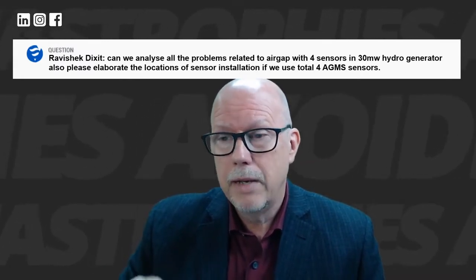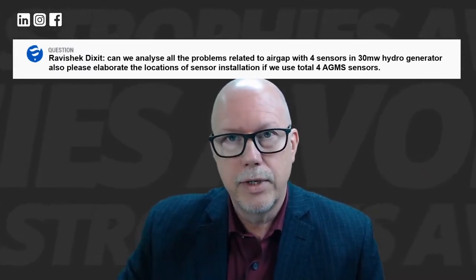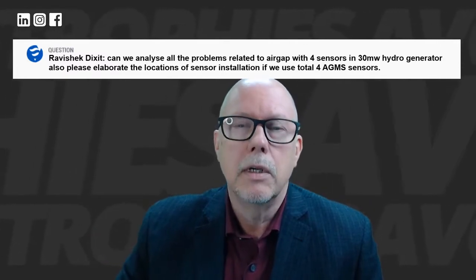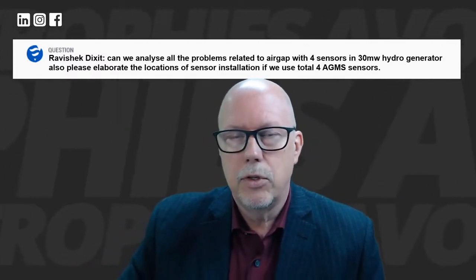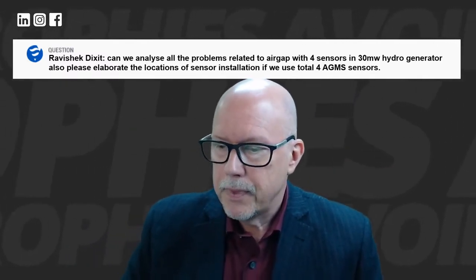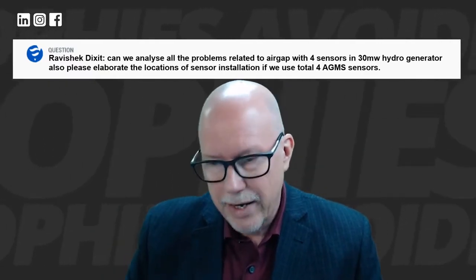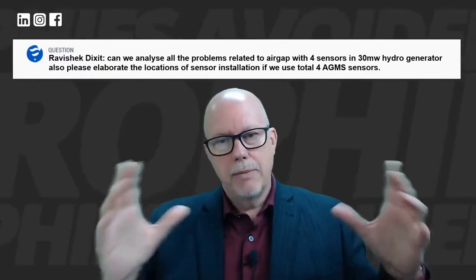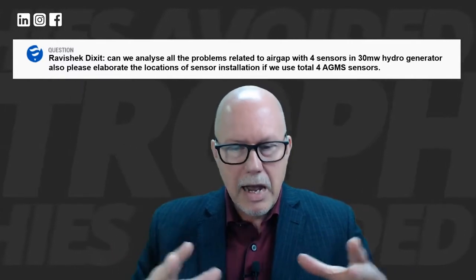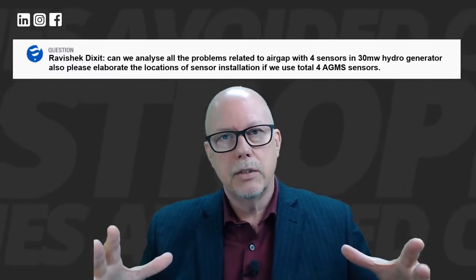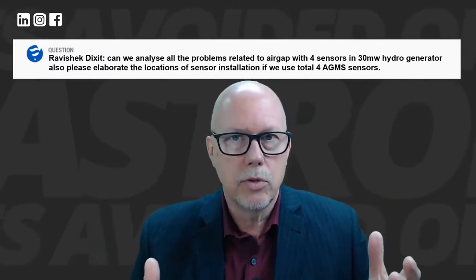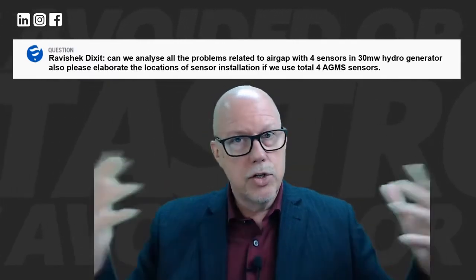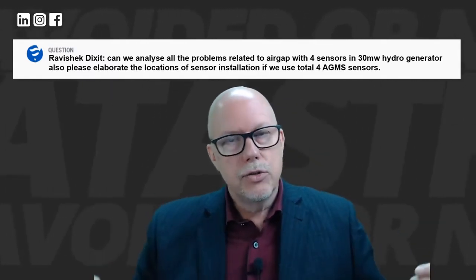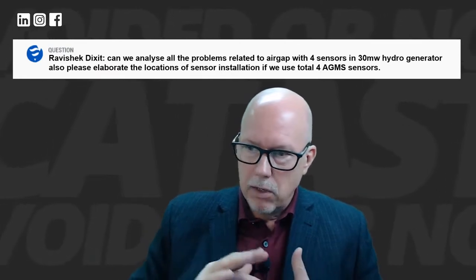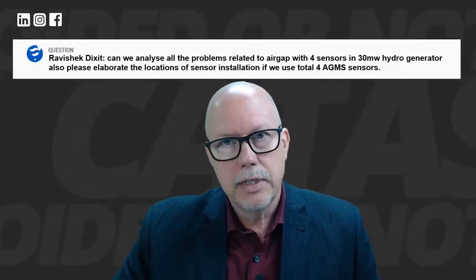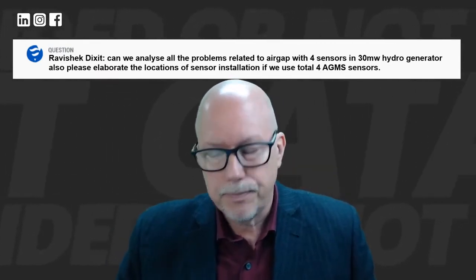I mean, the OEM has to validate that what they're delivering actually works as promised. You can't do that if you don't have any data whatsoever. Now, if we go back to how many sensors and locations, that's a question of geometry. The size of the unit will determine how many sensors you want to put all the way around. The larger the unit, the more sensors you need, because you want to avoid having large sections of the stator that are not being monitored.